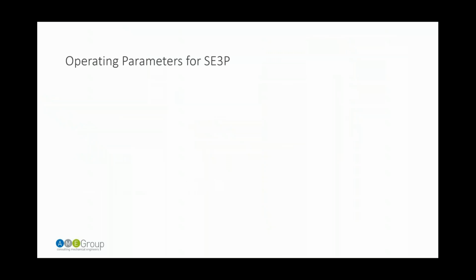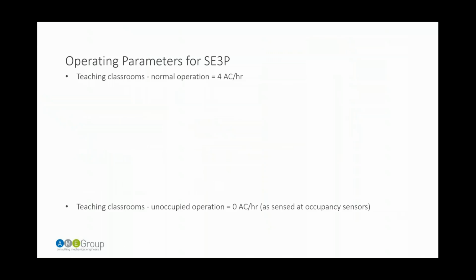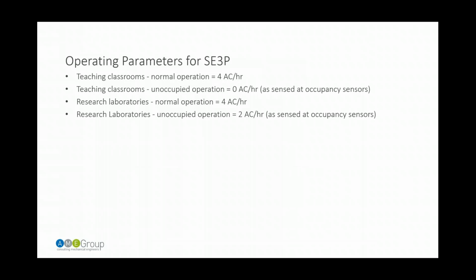And so from this, we looked at the operating parameters for the airflow in the labs and came to the following things, which were 4 air changes per hour for normal operation in both our teaching and our research laboratories, and obviously ramping up. And then in the teaching classrooms, unoccupied operation, which was going to be identified through occupancy sensors that are taking off of the lighting sensors, would be just 0 air changes. So we just turn things off when people aren't using the teaching classrooms.